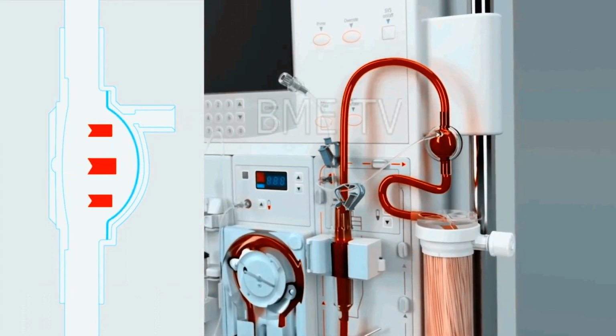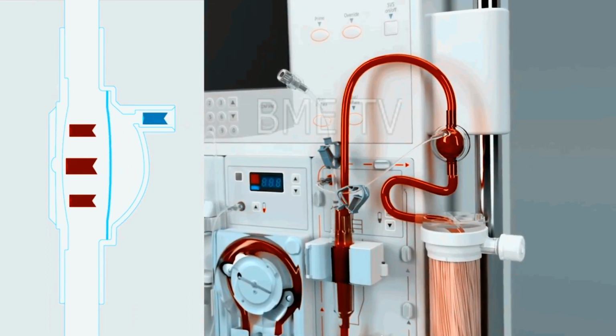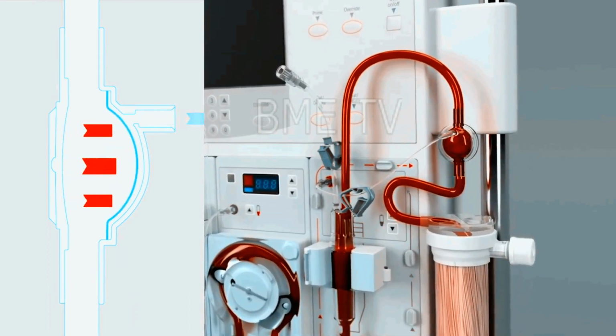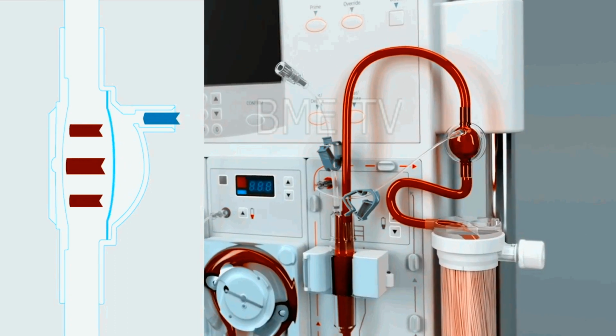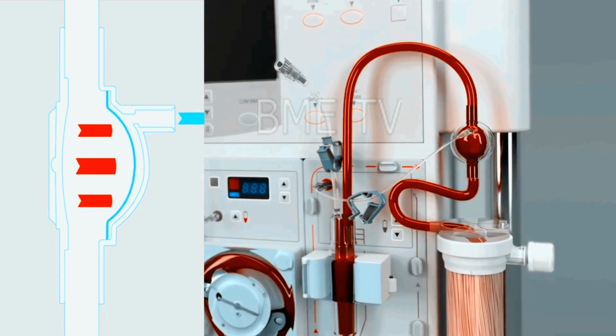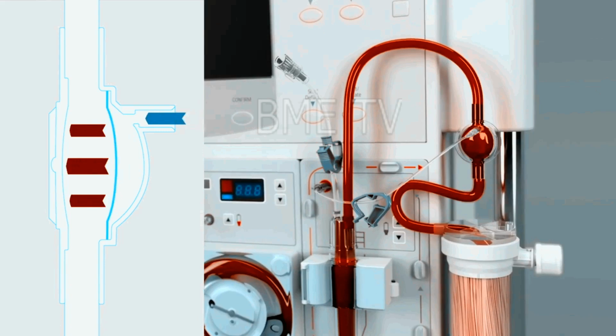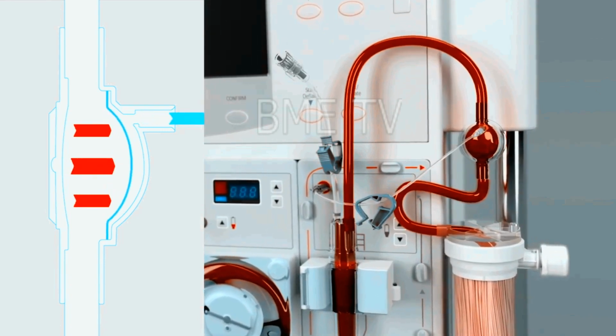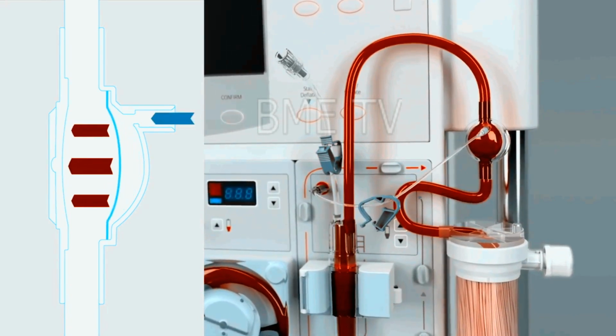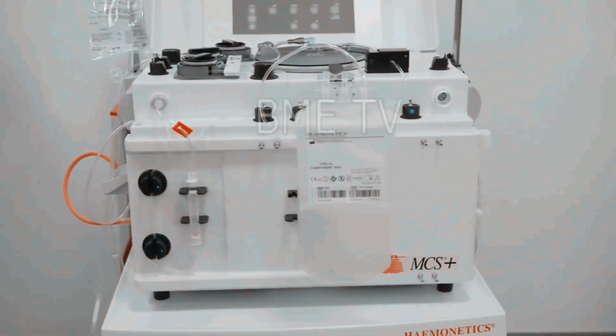The second method is intermittent flow centrifugation. Intermittent flow centrifugation works in cycles, taking blood, spinning and processing it, then giving back the unused parts to the donor in a bolus. The main advantage is the single venipuncture site. To stop the blood from coagulating, anticoagulant is automatically mixed with the blood as it is pumped from the body into the apheresis machine. And the third method is continuous flow centrifugation.